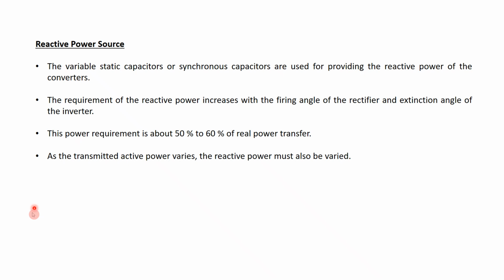The requirement of reactive power increases with the firing angle of the rectifier and the extinction angle of the inverter. We know that in thyristor operation, a firing angle is required. So whenever this firing takes place, there is a large reactive power requirement because they consume reactive power. If reactive power is not there in sufficient amount, then it will not be able to operate these machines or converters. So these reactive powers are required.